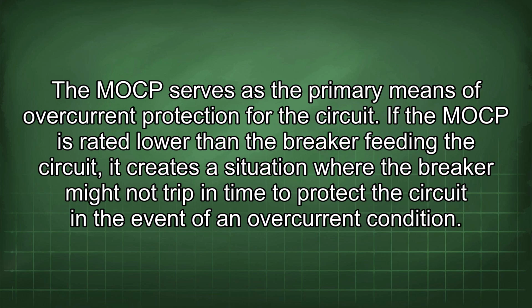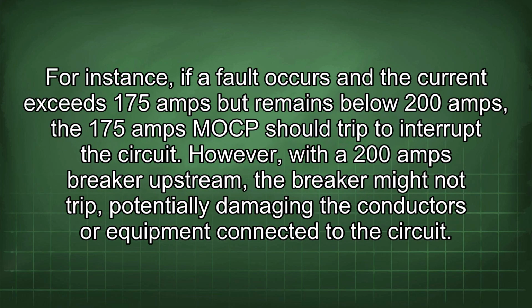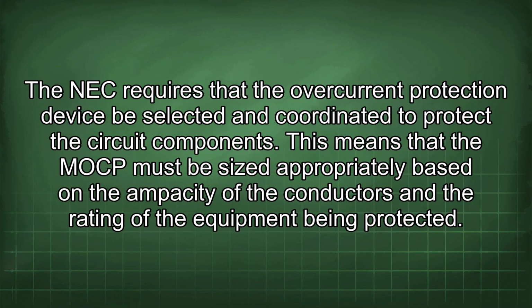If the MOCP is rated lower than the breaker feeding the circuit, it creates a situation where the breaker might not trip in time to protect the circuit in the event of an overcurrent condition. For instance, if a fault occurs and the current exceeds 175 amps but remains below 200 amps, a 175 amps MOCP should trip to interrupt the circuit. However, with a 200 amps breaker upstream, the breaker might not trip, potentially damaging the conductors or equipment connected to the circuit. The NEC requires that the overcurrent protection device be selected and coordinated to protect the circuit components.